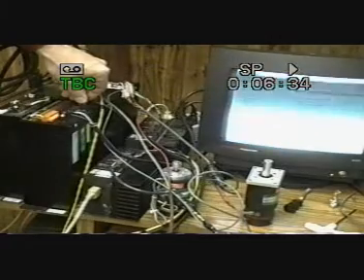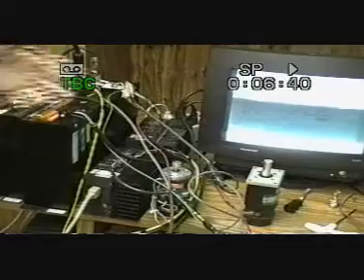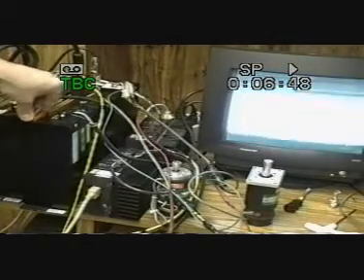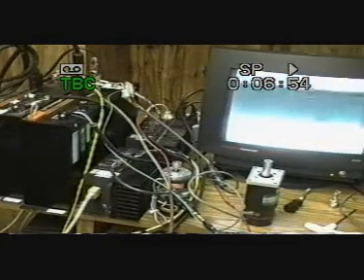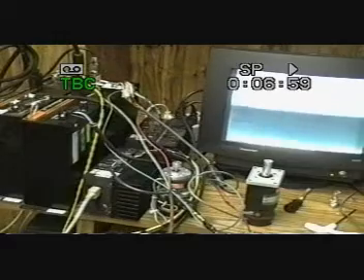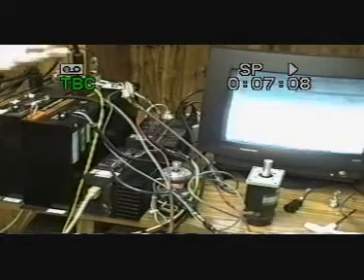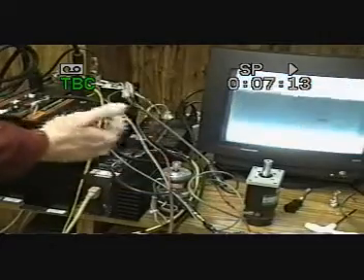We have to do a power on reset or a hard reset on the software, and you'll see that that indeed power up. We are not getting an encoder fault. Our press motor is running, and our gripper will follow. But because we have a degraded encoder input on P4, we will eventually, and I've had it go from 10 seconds to 2 hours, we'll eventually get an encoder 2. I have picked the speed of the press for a reason.